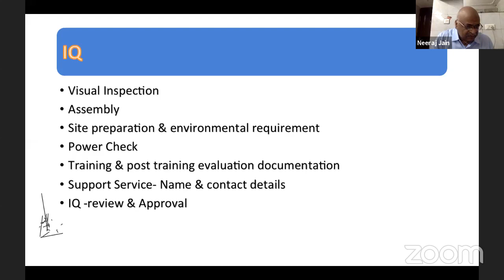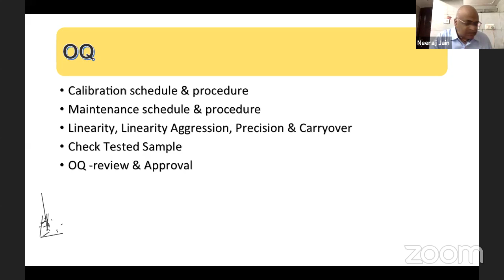Then this IQ data is approved and reviewed by some authorized person. Then you have installed your machine, but your machine is not ready for operation. You need calibration schedule and procedure, maintenance schedule and procedure. We discussed daily, weekly, and monthly maintenance, how to carry out all those things. Then do linearity, precision, carryover, and document in your laboratory, then you will get performance characteristics. And you see whether your performance characteristics are close to performance specifications or not. Then check with control. Then check with already tested samples. Now your machine is ready for operation.